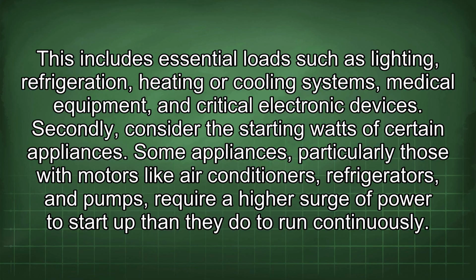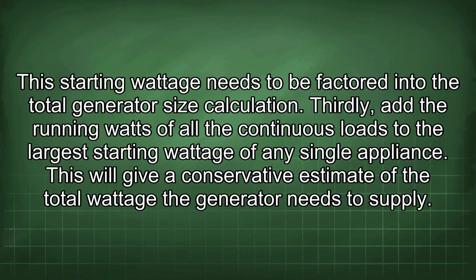Secondly, consider the starting watts of certain appliances. Some appliances, particularly those with motors like air conditioners, refrigerators, and pumps, require a higher surge of power to start up than they do to run continuously. This starting wattage needs to be factored into the total generator size calculation. Thirdly, add the running watts of all the continuous loads to the largest starting wattage of any single appliance. This will give a conservative estimate of the total wattage the generator needs to supply.